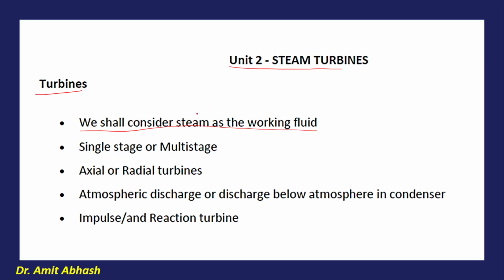Especially when talking about steam, that means instead of steam I should say vapor, and the dryness fraction should be greater than a certain value, meaning it should not be in the wet region, because it will corrode the blade part, and that is very dangerous for the life of the turbine. This is the main point of concern.